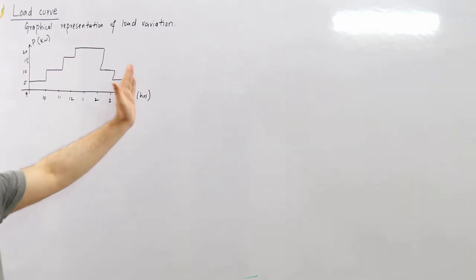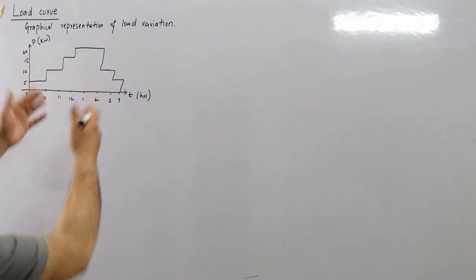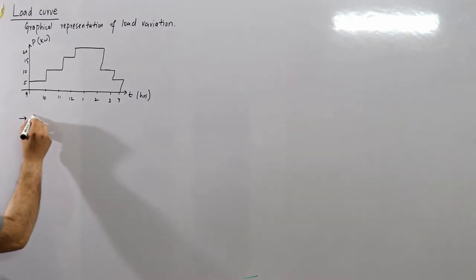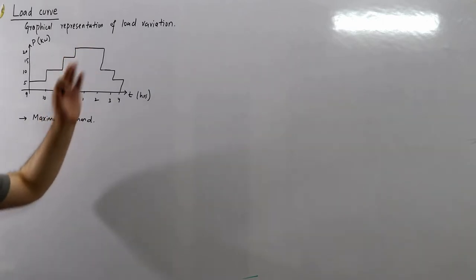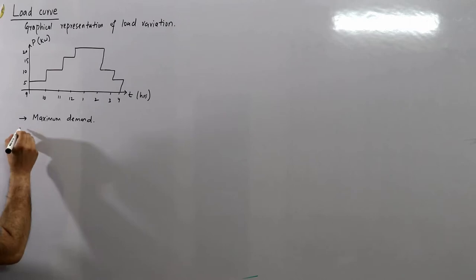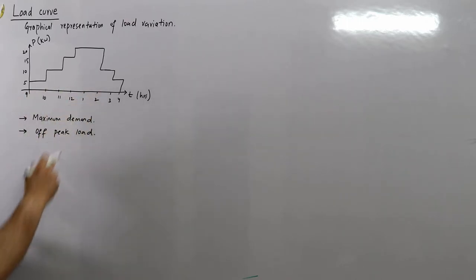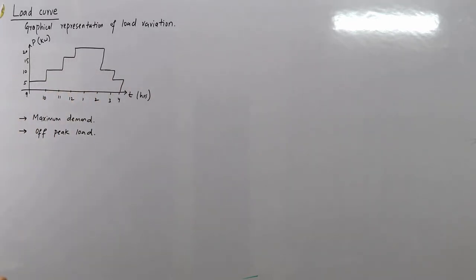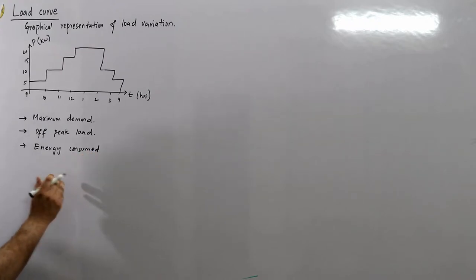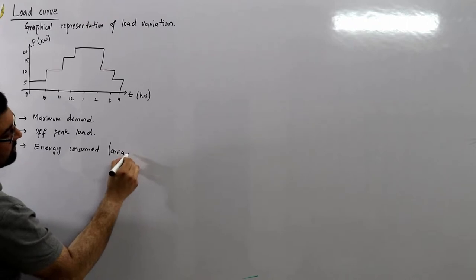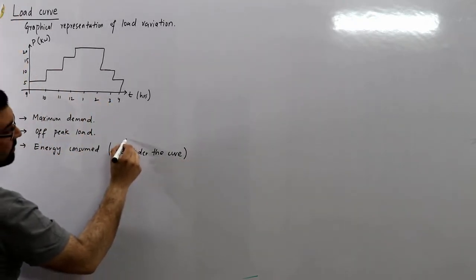From the load curve, you can directly state a number of quantities. The first would be maximum demand - the highest point on the load curve, the peak load. From here you can see it's 20 kilowatts. The second is the off-peak load, or minimum load, which in this case is 5 kilowatts. Third, you can find the energy consumed from the area under the curve, because this is a rectangular graph and power into time gives you the energy.